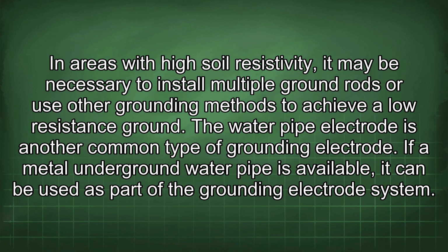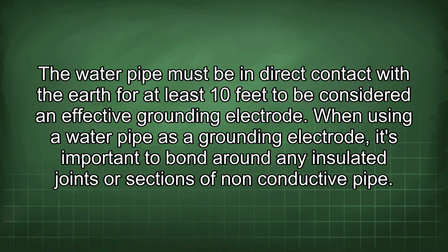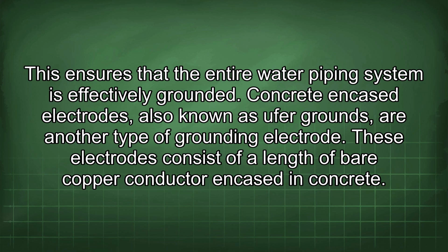If a metal underground water pipe is available, it can be used as part of the grounding electrode system. The water pipe must be in direct contact with the earth for at least 10 feet to be considered an effective grounding electrode. When using a water pipe as a grounding electrode, it's important to bond around any insulated joints or sections of non-conductive pipe. This ensures that the entire water piping system is effectively grounded.